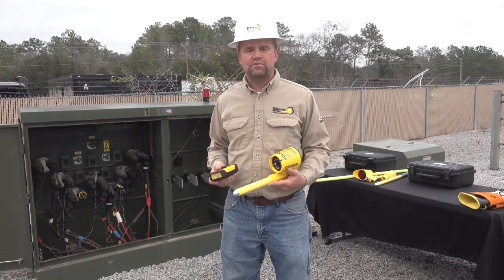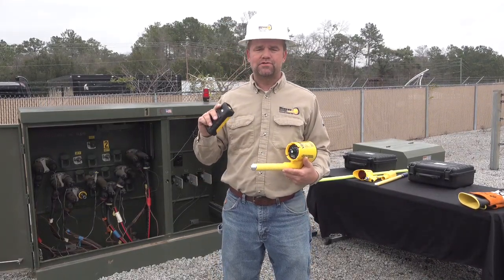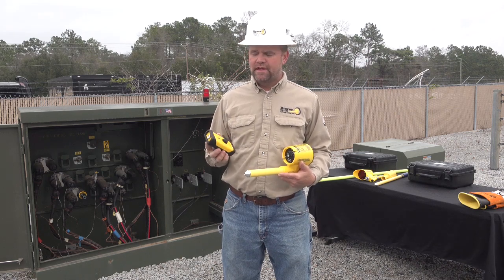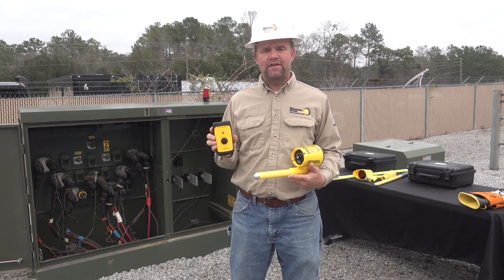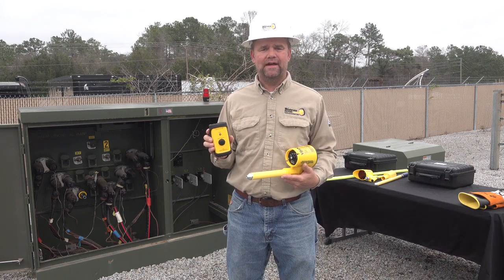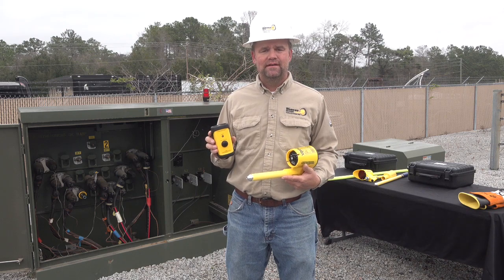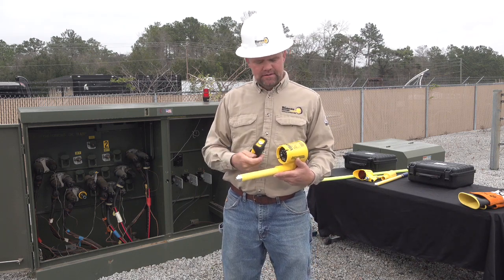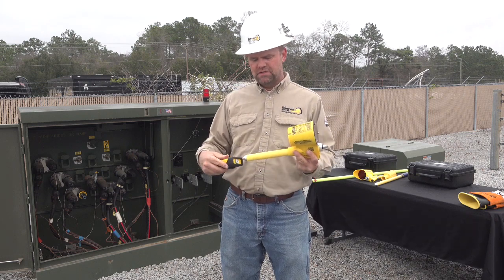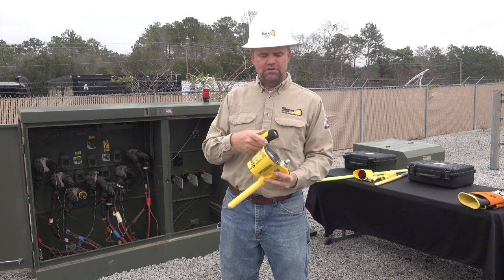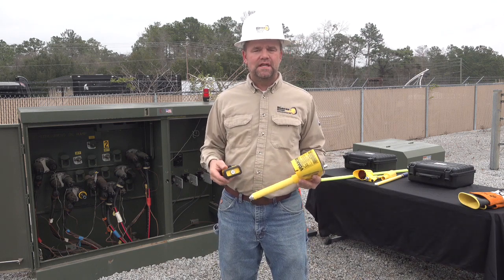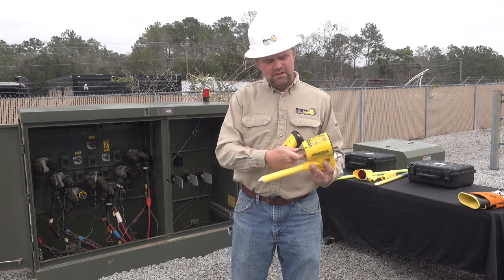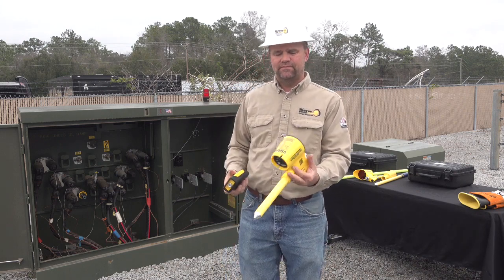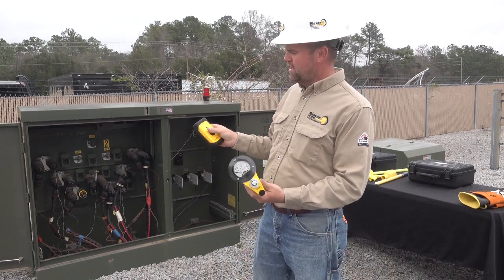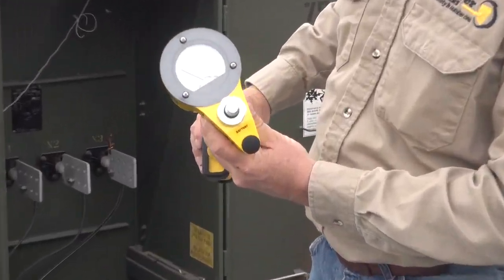Also, before and after each use, we encourage the user to actually use a true known voltage. You can do that by using the device here that we manufacture. It's referred to as a handheld power supply. The part number is HHPS. This device will output a known voltage to our voltage detector, our VDAH300, and it should deflect near 7 kV. So again, we encourage you to use this before and after each use. Simply turn the device on to the first position, hold the button on the handheld power supply to where you have a green light, touch the end of the probe, and again the needle should deflect near 7 kV.